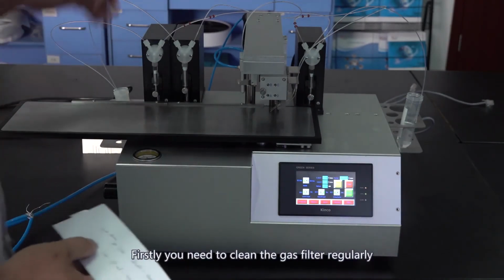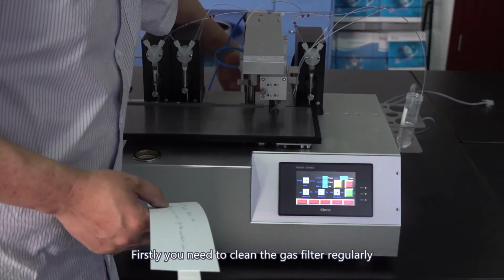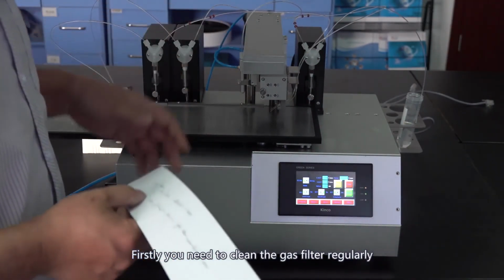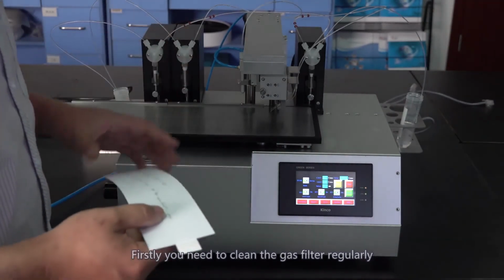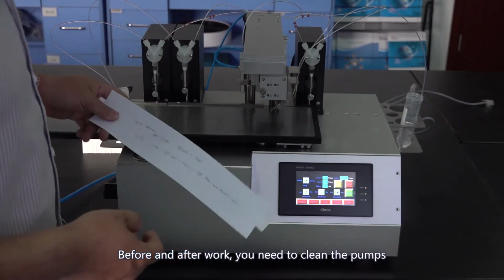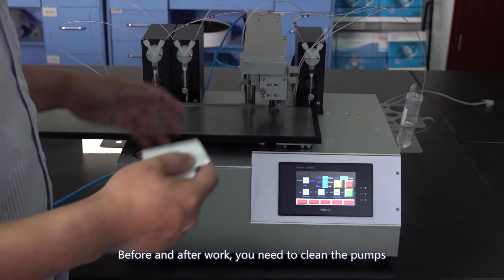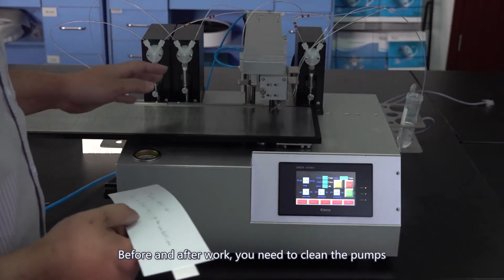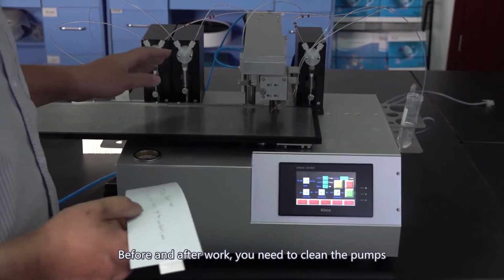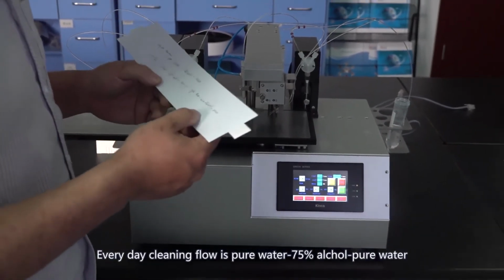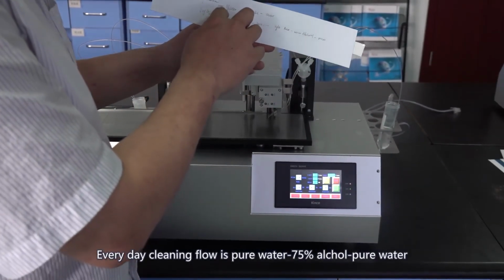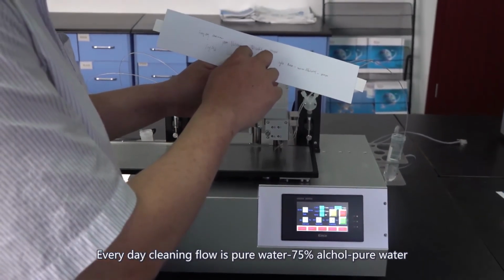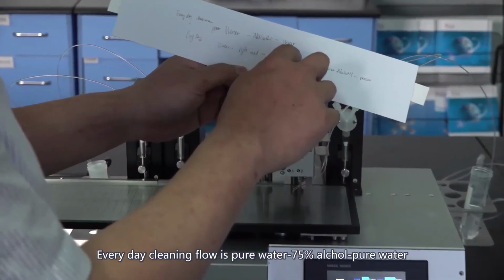First there is the gas filter. You can clean the gas filter sometimes. Here is a pump. Here is a pump. You need to clean it every day before and after work. The process of everyday cleaning is the water, 75% alcohol, and water.